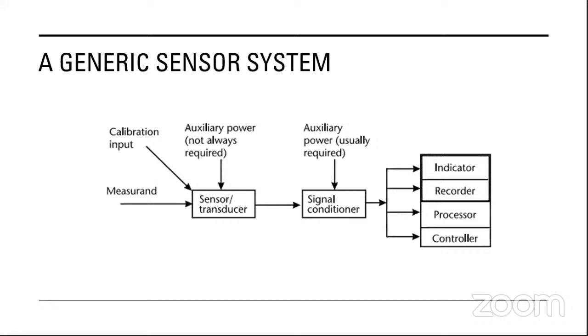External signals can interfere with it and kill the signal generated from the sensor. Therefore, you need a signal conditioning unit which filters out unwanted signals or unwanted frequency components, and amplifies the necessary frequency component or signal. The signal conditioning unit will also have a thresholding mechanism or some other mechanism to understand how much was sensed, or what quantity or measure the sensor made. It then feeds this to an indicator, a recorder, a processor, or a controller.